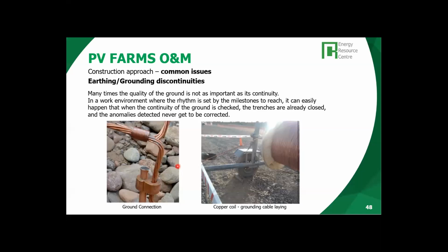So sometimes the time becomes pressing in the construction work. And the problem is that the civil works sometimes are finished before the electrical testing and commissioning takes place. And then if some defects are detected, it can be a little bit difficult to reopen trenches, go back to the contractors and the civil works, etc.